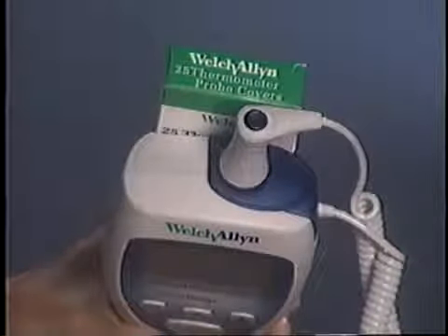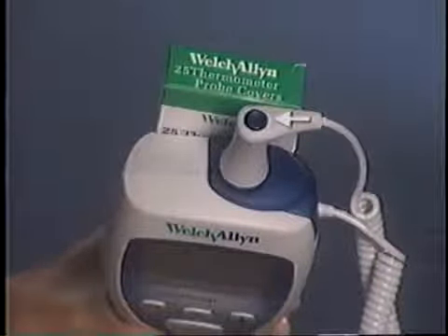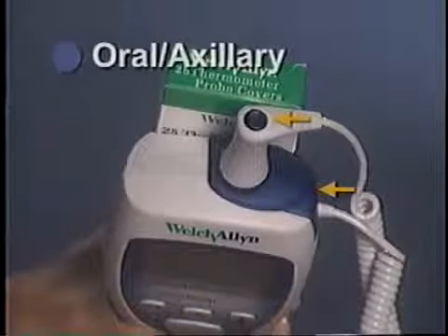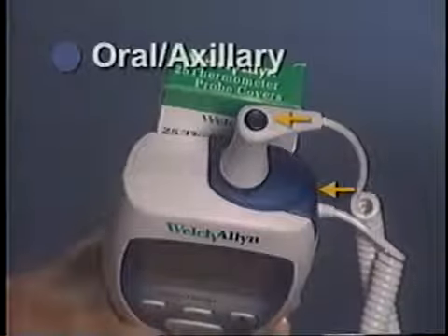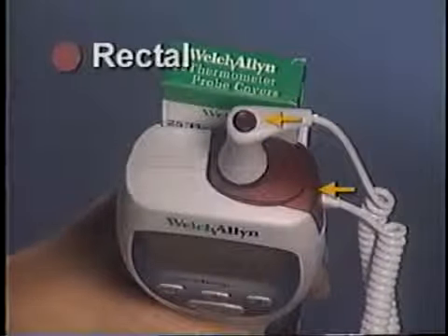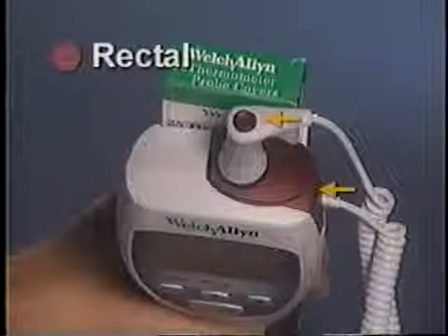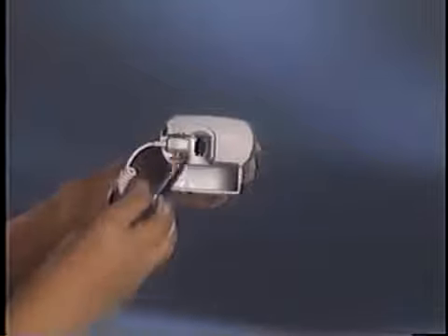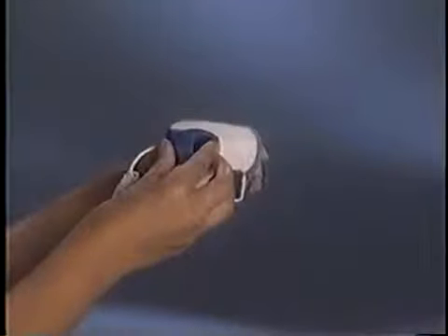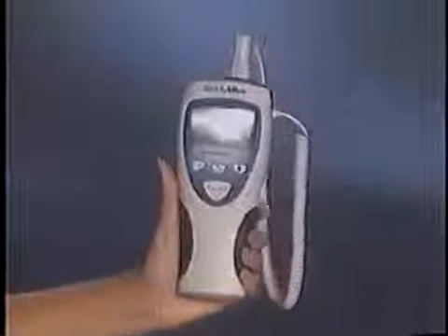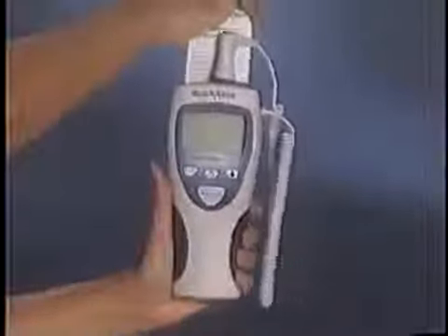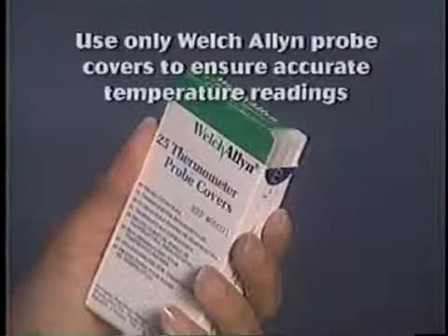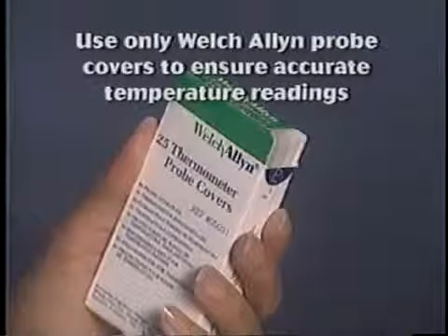Begin your use of the thermometer by attaching the probe connector. A probe with a blue ejection button and blue probe well are used for oral or axillary temperatures. A probe with a red ejection button and a red probe well are used for rectal temperatures. Attach the probe connector, making sure it's secure. Next, insert the removable probe well into the thermometer. Then place the probe in the well. Insert a box of Welch Allyn disposable probe covers into the storage well of the thermometer. Use only Welch Allyn probe covers to ensure accurate temperature readings.